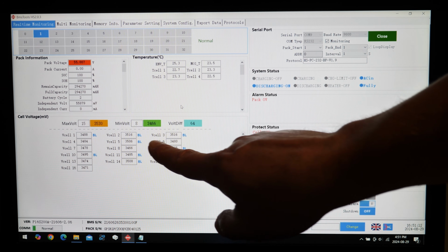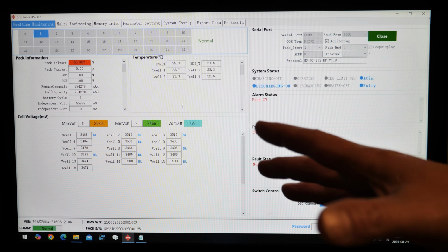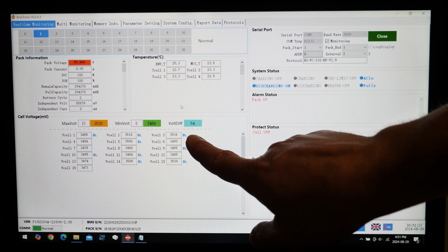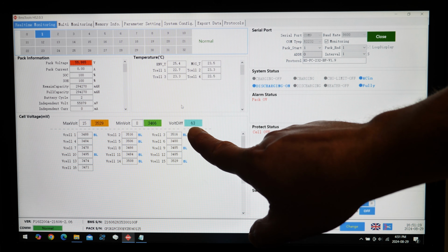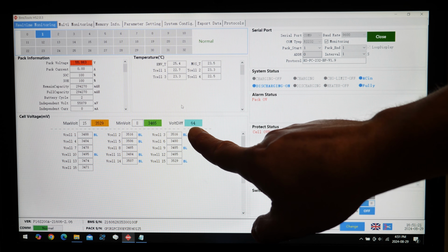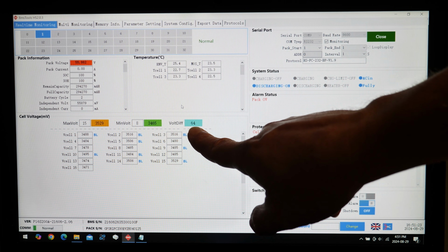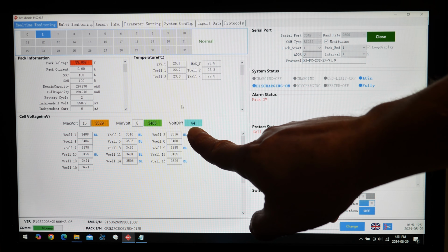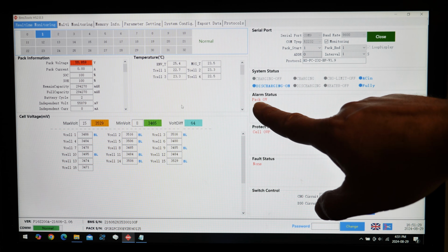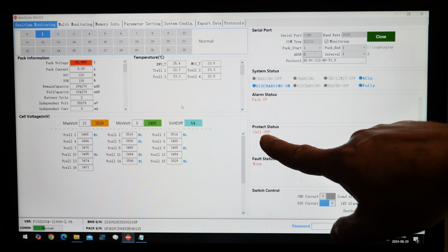If we look down here, we do have a couple of cells balancing, again this is without the active balancer. Our cell differential is 63 to 64 millivolts, which in my opinion is fan-freaking-tastic. So it just shut off with a pack over voltage and basically a cell over voltage. So that's where we're sitting at right now.